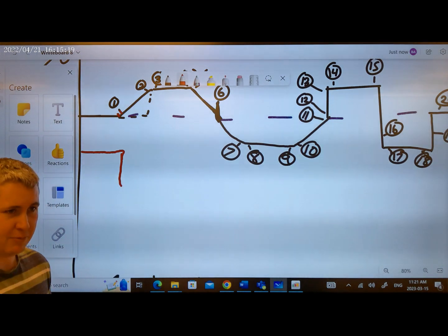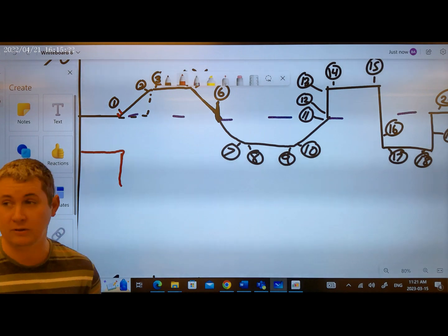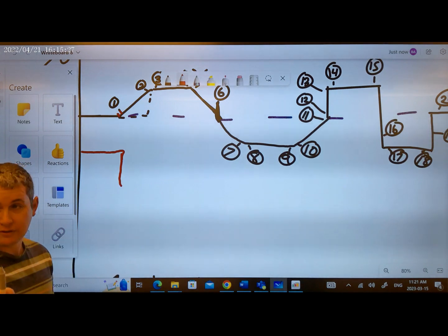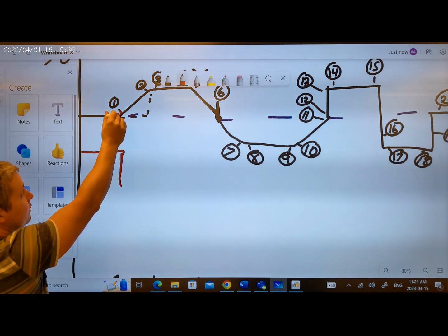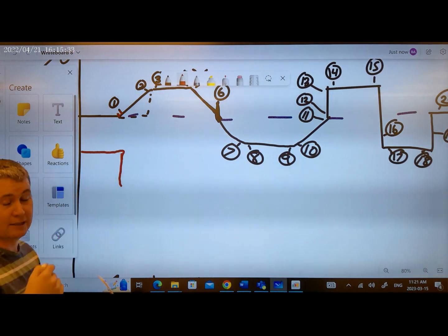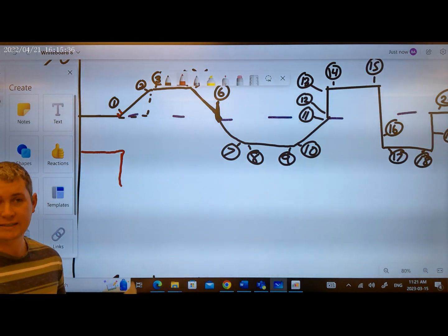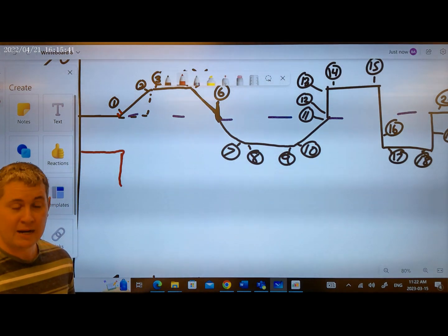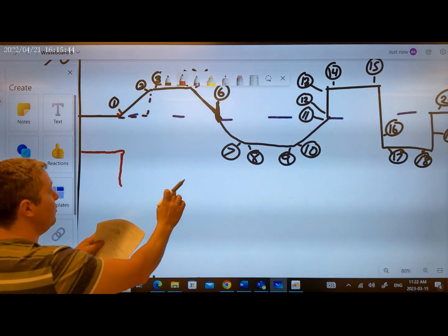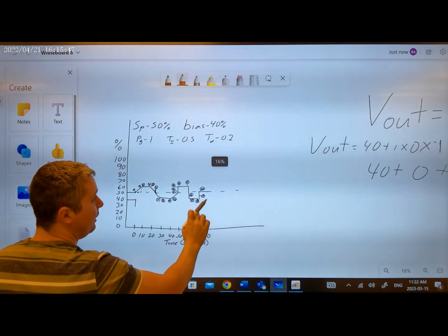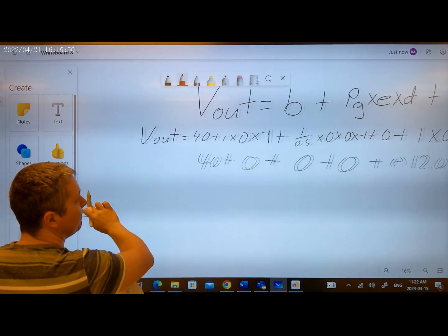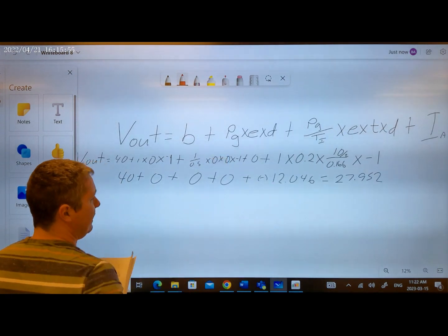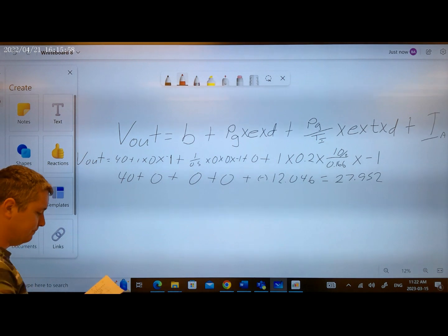As soon as it starts that ramp rate and the controller has time to calculate, it says, oh, you're supposed to be down here because of derivative. Not because there's no integral that has taken place. The proportional still hasn't done anything because it hasn't really deviated from its set point. But the derivative sees a ramp rate, and so it drops our output by 12.046. Okay, so now we're looking at point number 2.